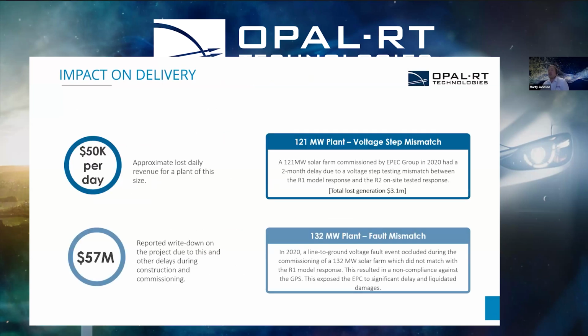In terms of the impact on delivery, we have an example where, when commissioning a particular solar farm, there was a 2-month delay due to a mismatch in the voltage step test, similar to the one we saw before. For a plant this size, that can be up to $50,000 per day in lost revenue.